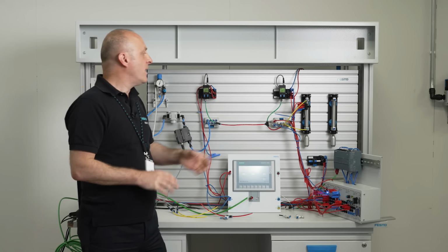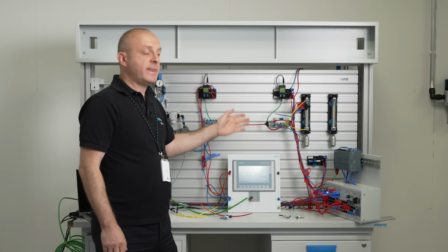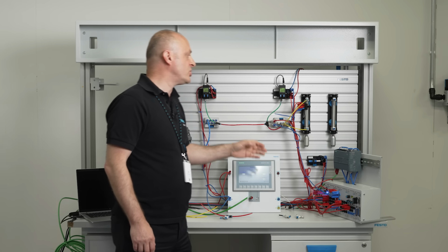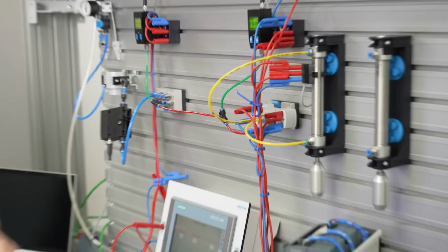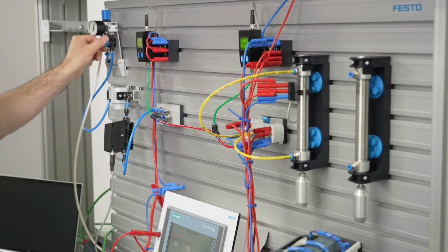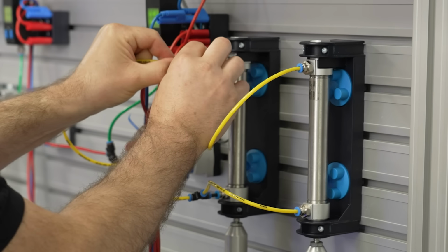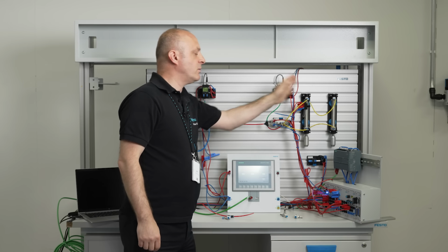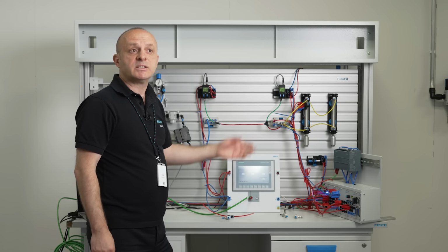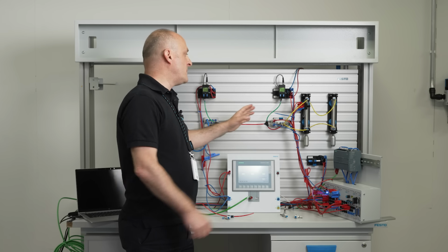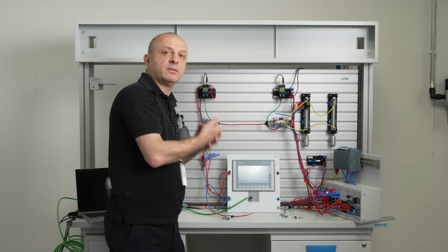This time, I've taken my flow control valves out. We have only one machine, we will run it, and then we will add another machine, that cylinder represents the second machine, and have a look at the pressure drops again. Press the button. You see our first machine is working all right. I will stop it and turn the air off. Everything is the same, but we have added one more machine, so our second machine is also working. I will start the cycle. It started and stopped. We have a fault because we couldn't provide enough pneumatic power again, because the second machine is taking more flow.